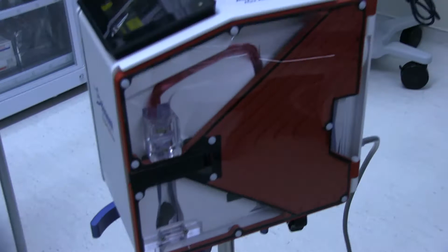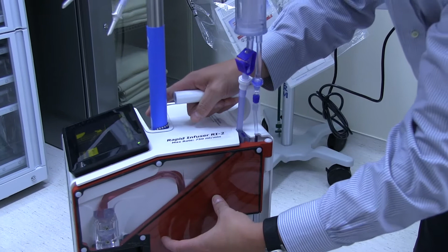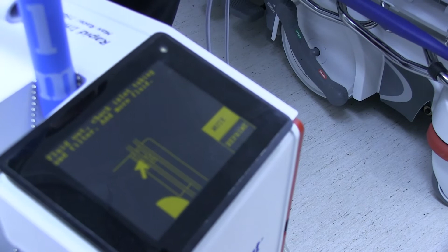When the reservoir runs dry, air hits here, and it clamps itself shut. So now you have a bunch of air in the set, but the air never had a chance to get introduced to the patient line. So it's trapped in here, so you can stay connected to the patient. The prompt tells you: fluid out, check inlet tubing and filter, add more fluid. So you just make sure that the inlet tubing is not kinked off. Your filter's good because you didn't add any cryo or platelets.